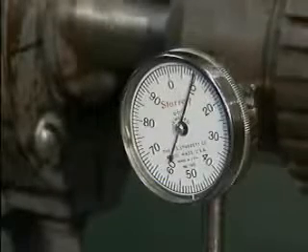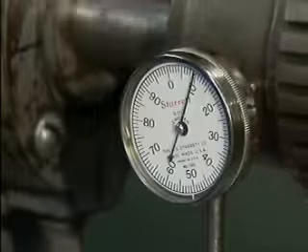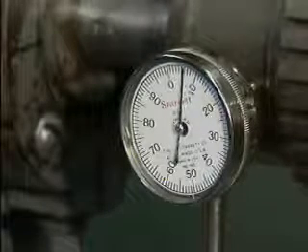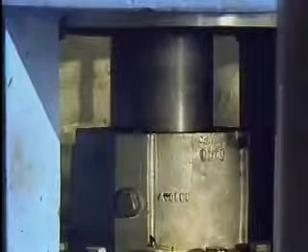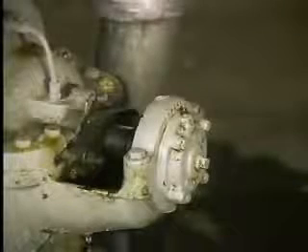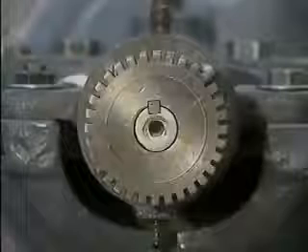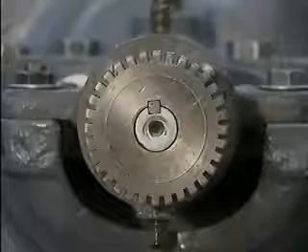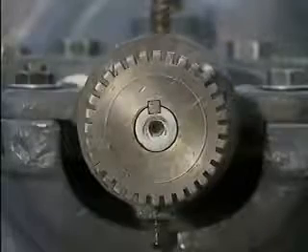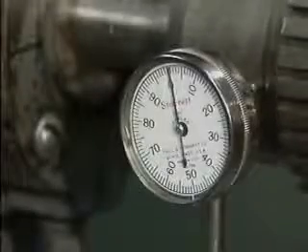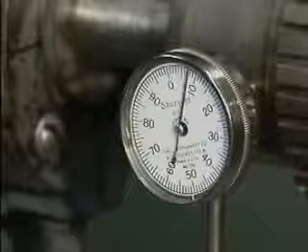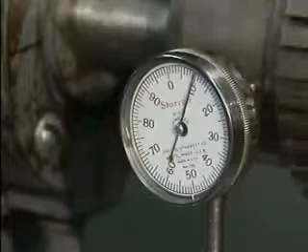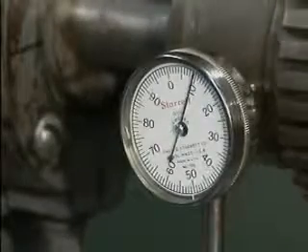A shaft typically has some run-out or eccentricity during its rotation. However, too much run-out is an indication of a problem. For example, a bent shaft or worn or damaged bearings could cause eccentric rotation of the shaft. A defective coupling that's out of round could also cause an excessive run-out reading. Facilities generally specify the amount of run-out that's allowable. If readings exceed the allowable limit, the cause of the problem will need to be determined.